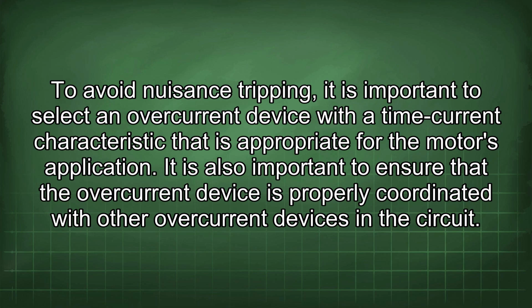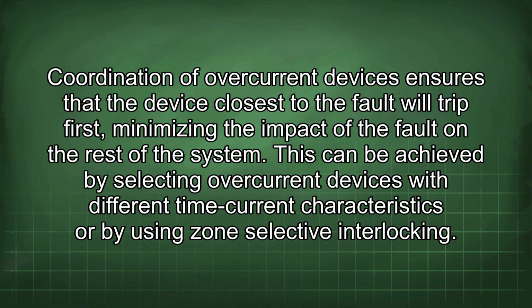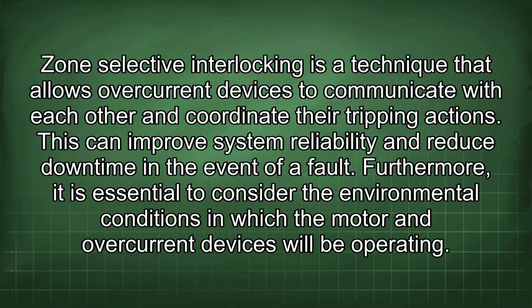To avoid nuisance tripping, it is important to select an overcurrent device with a time current characteristic that is appropriate for the motor's application. It is also important to ensure that the overcurrent device is properly coordinated with other overcurrent devices in the circuit. Coordination of overcurrent devices ensures that the device closest to the fault will trip first, minimizing the impact of the fault on the rest of the system. This can be achieved by selecting overcurrent devices with different time current characteristics or by using zone-selective interlocking. Zone-selective interlocking is a technique that allows overcurrent devices to communicate with each other and coordinate their tripping actions. This can improve system reliability and reduce downtime in the event of a fault.